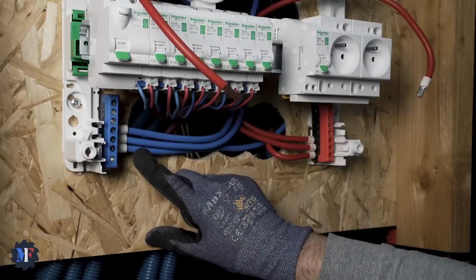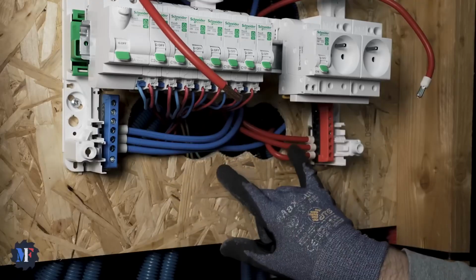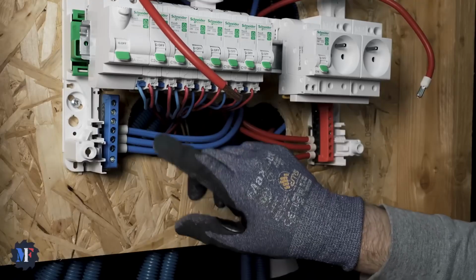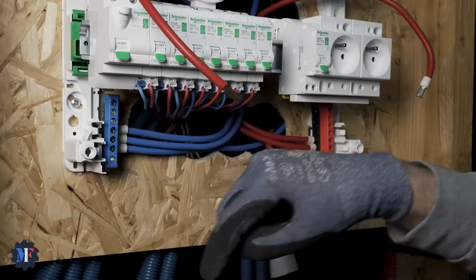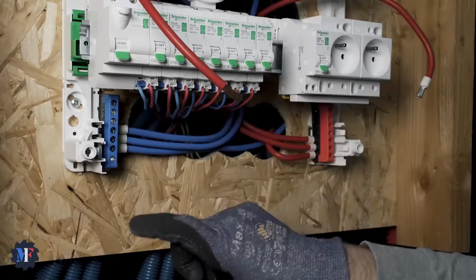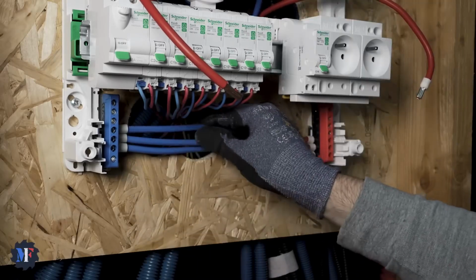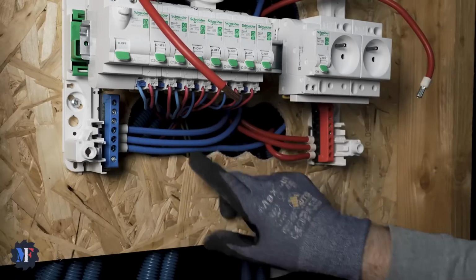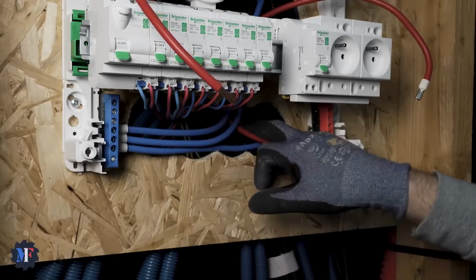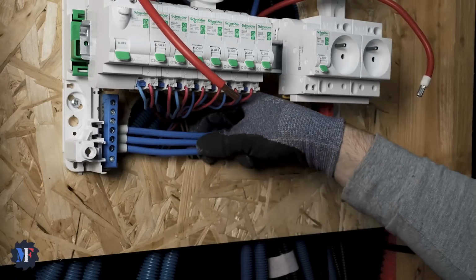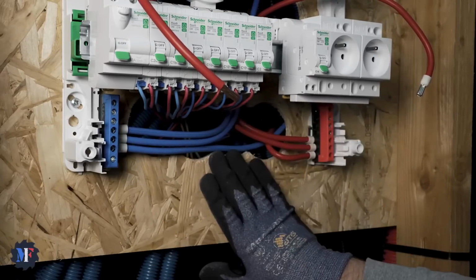The power supply comes from the lower panel in 16mm2. Then I have my first row of differential breakers that will supply the second, third and fourth, with the bus bars and my differential breaker on module 5. And the same for the phase. As for this, we'll see what we do with it, you'll see that later. So for now, the 16mm2 is done.